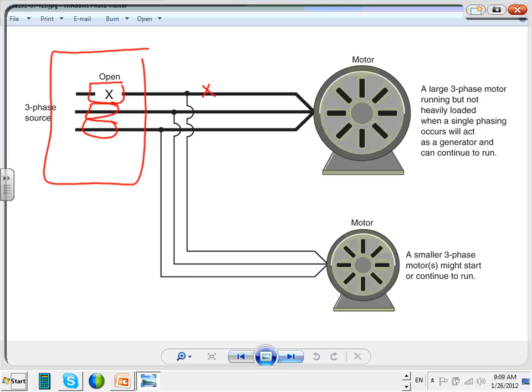If you have major motors, guys, big motors, let's say a 100 horsepower motor, and I have here a 10 horsepower motor. If you lose the fuse while the motor is running, but it's lightly loaded, the motor is rated for 100 horsepower, but the machine that's running off it is worth, say, 50, right? So the motor is rated for 100, the machine is rated for 50 horsepower. So it's half loaded. In a situation like this, and it's running, guys, it will continue to run. At one time it will heat. And by the way, it acts as a generator and brings a third phase to the smaller motor, and the smaller motor continues to run too.